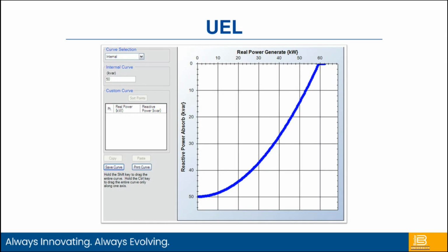Here's a BESTCOMS screenshot of our under excitation limiter. This is basically comparing the amount of reactive power that I can absorb in comparison to the real power output of that particular machine. So I'm creating a curve, adding the two parameters to make sure I'm within the capabilities of my generator. This can be set up as a fixed curve, or we can do multiple points to get very custom curves. The DECS allows up to 5 points to set the under excitation limit.